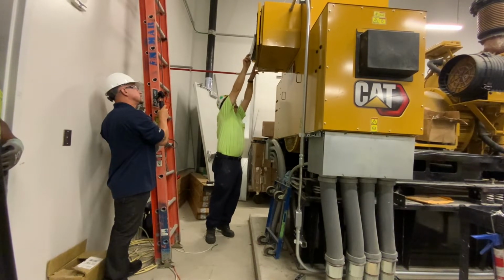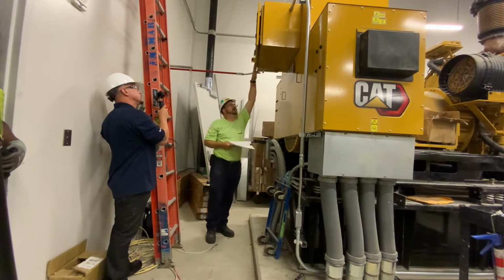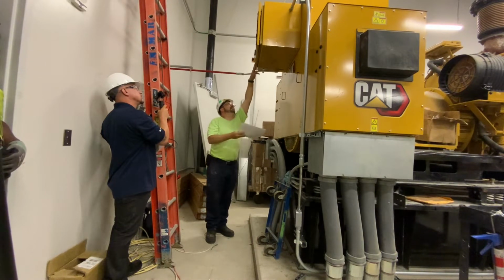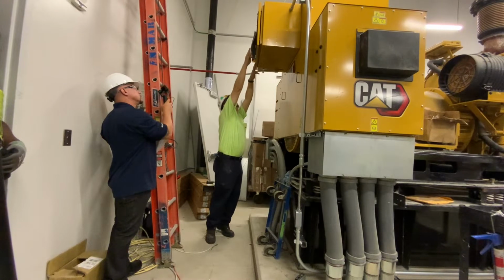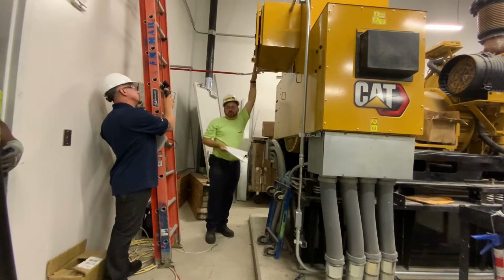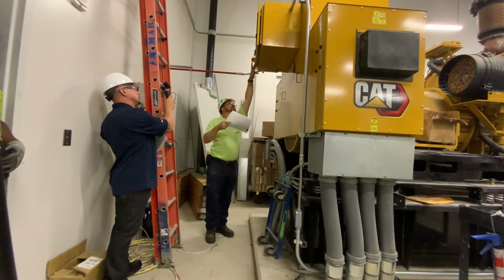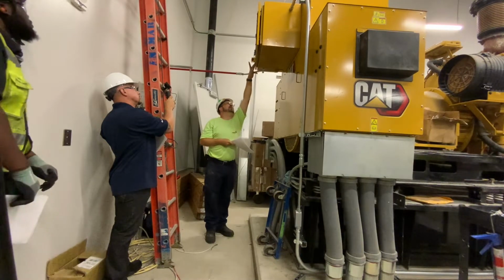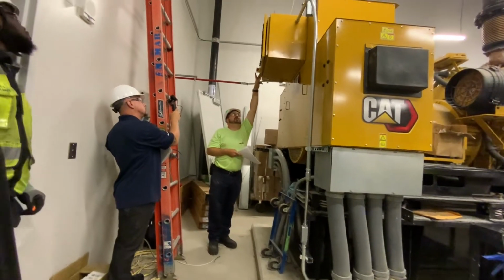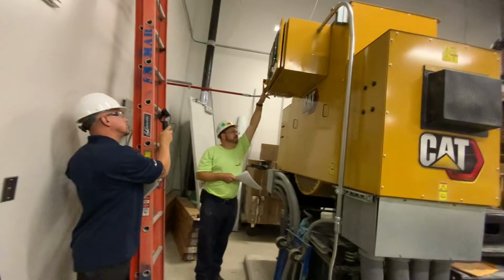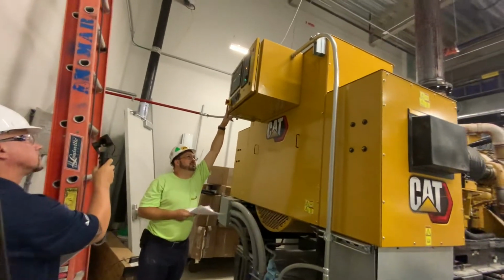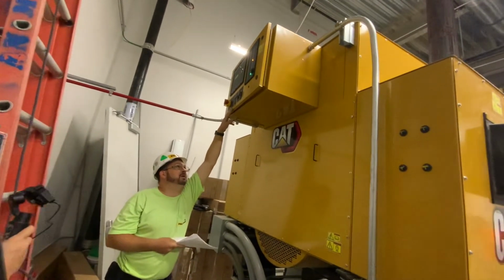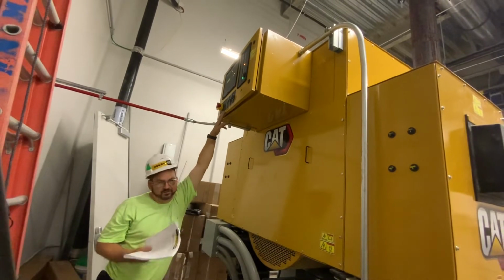Way up top here, the amber light is a warning light. The button underneath that is the silence button. The next indicator over is red—that's for all shutdowns, it'll light up red there. The button underneath the red indicator is the reset button, so when you push that, you're able to reset the shutdown fault. Keep in mind, you have to clear the fault first.